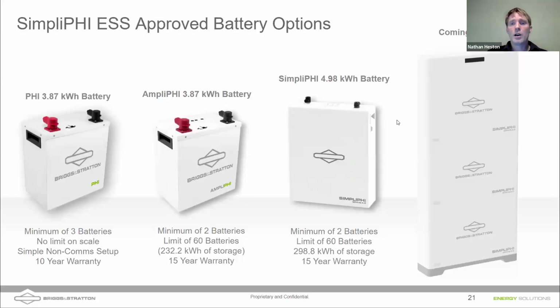So I'm showing you 4 different battery offerings we have now. These are our 48-volt battery options. We also have high voltage batteries, but that's not the subject of this talk. Our smaller format batteries come in at 3.87 kilowatt hours. These are both indoor rated batteries. However, we have the ability to put both of those batteries in our outdoor rated enclosure, either in a Boss 6 cabinet or a Boss 12 cabinet that can hold 6 versus 12 batteries.